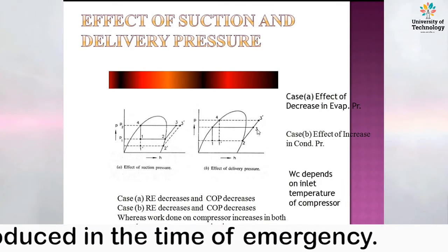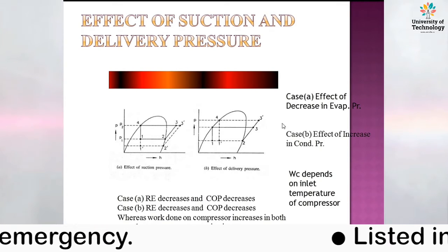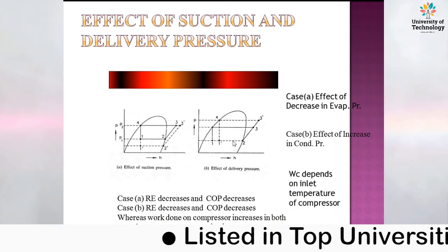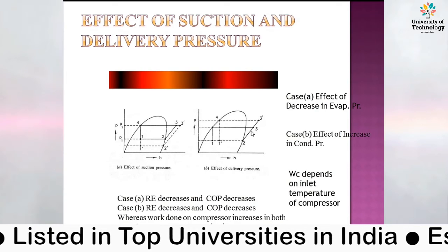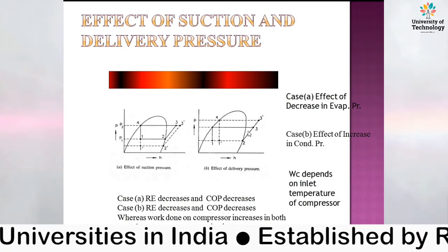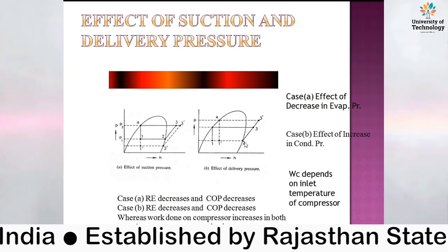So what we observe in this case: refrigerant effect decreases, compressor work increases, COP decreases, pressure ratio increases, volumetric efficiency decreases.